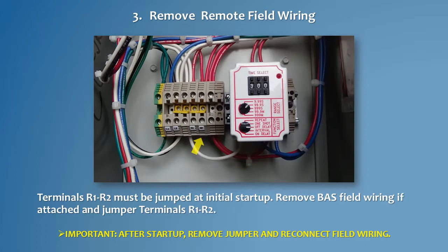Next, check to see if terminals R1 and R2 on the field access terminal board are jumped. If they are, nothing more needs to be done. If the terminals are not jumped but have wires connected to them, this indicates that a remote on-off relay is controlling the water heater from the building automation system. These wires must be removed prior to startup and the terminals must be jumped. Remember to remove the jumper and reconnect the remote wires after the startup is complete.